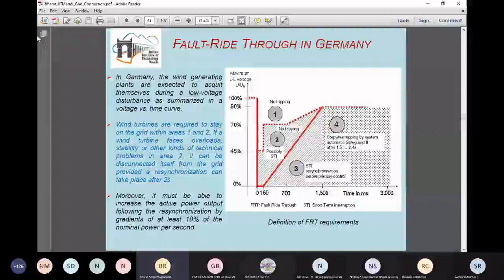But if the voltage is below the red thick line for a longer time, then in zone 3 and zone 4, disconnection of the wind farm or solar farm is possible, but in a phase-wise manner. After every 1.5 seconds, some 25% of the wind farm's given capacity can be disconnected. So this fault ride-through capability is given for the German grid code. Now, next slide, please.